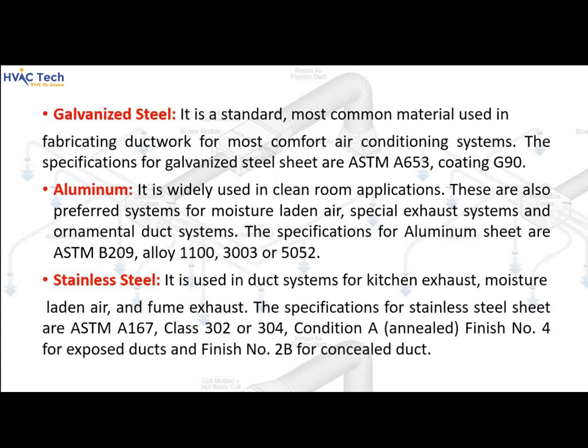Aluminum is widely used in clean room applications and is also preferred for moisture-laden air systems, special exhaust systems, and ornamental duct systems. The specifications for aluminum sheet are ASTM B209, alloy 1100, 3003, and 5052.